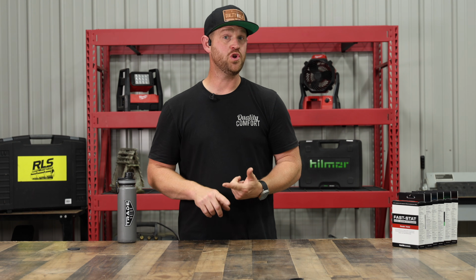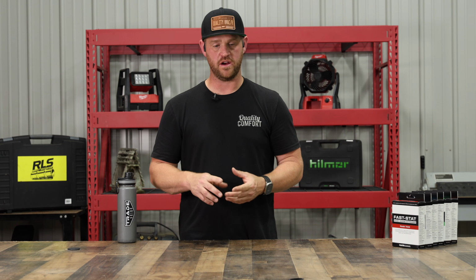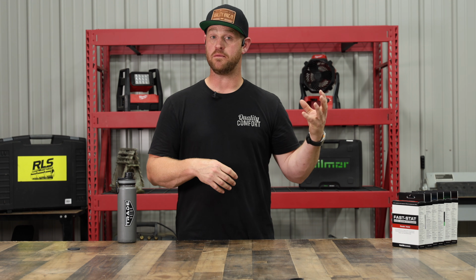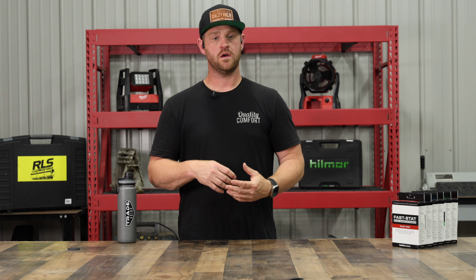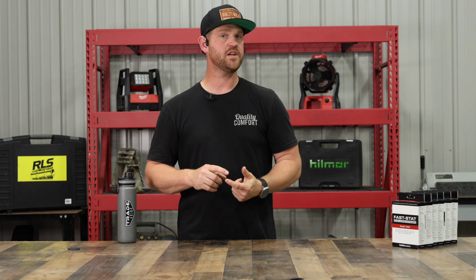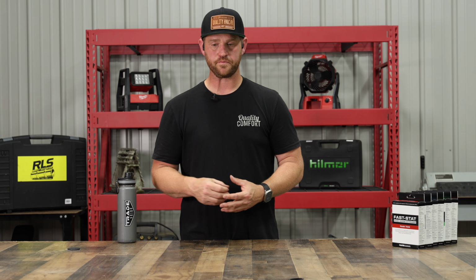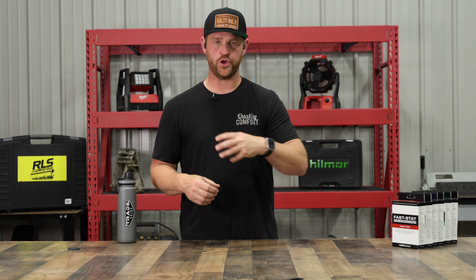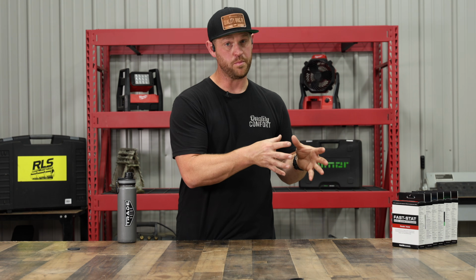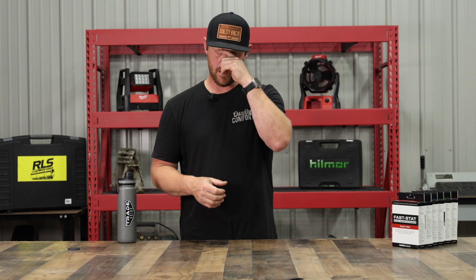You have full communicating systems, right? So therefore, it's more proprietary to the brand. Let's say it's a Trane unit. They're going to talk to one another. So it's not a 24-volt conventional thermostat cable, it's more of a communication cable. The thermostat, the indoor unit, and the outdoor unit all talk to each other, and that's how it operates. So you're pretty much stuck with their proprietary thermostats at that point. And whether they have the lockout function or not, I'm not sure. It just depends on what manufacturer you're going with.